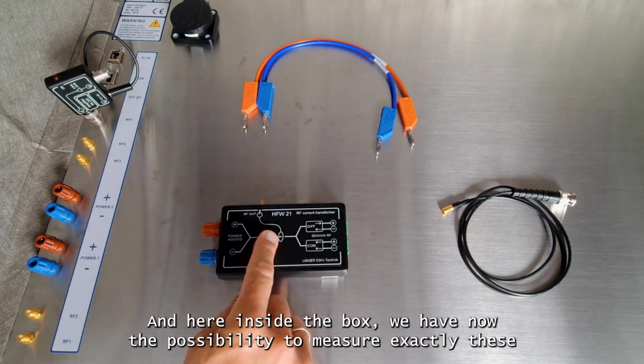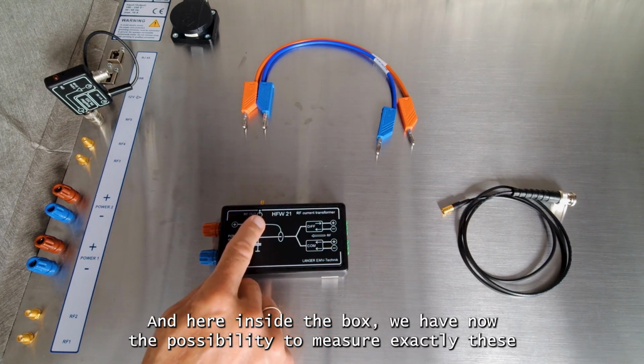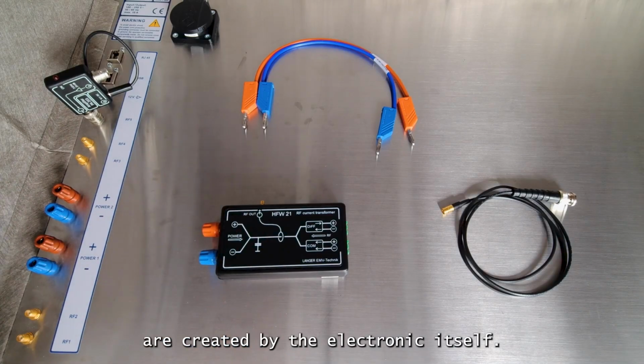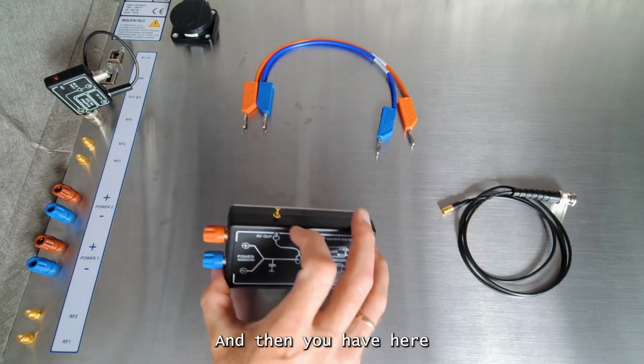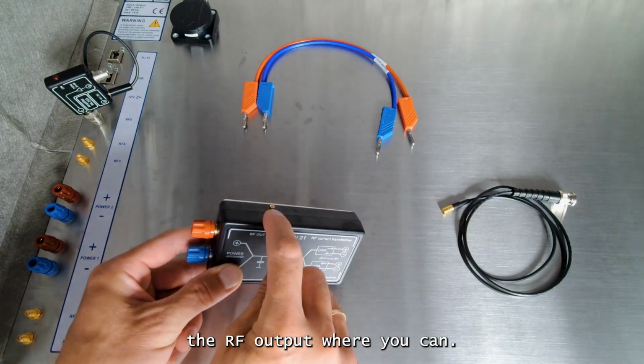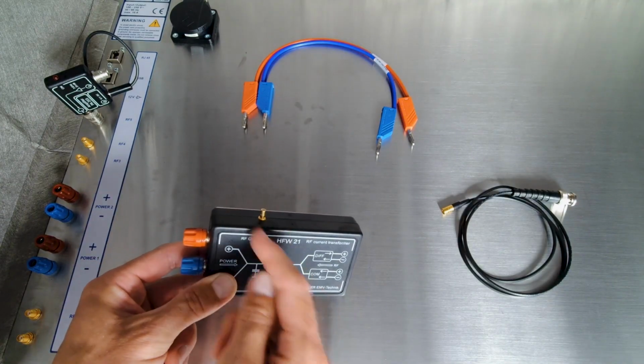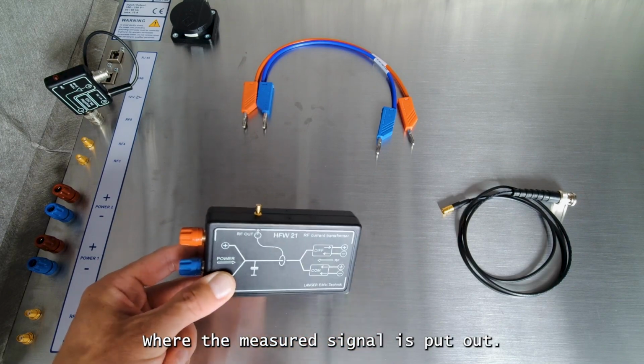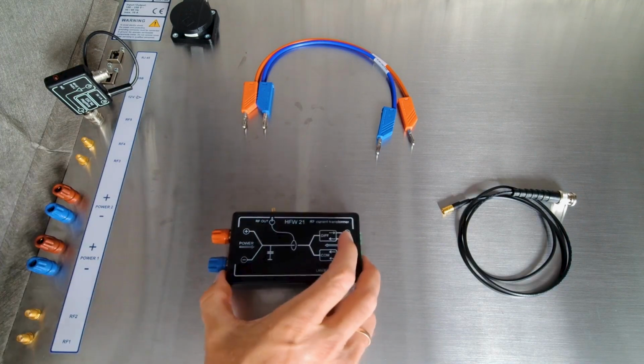And here inside the box we have now the possibility to measure exactly these disturbance currents which are created by the electronic itself. And then you have here the RF output where the measured signal is put out.